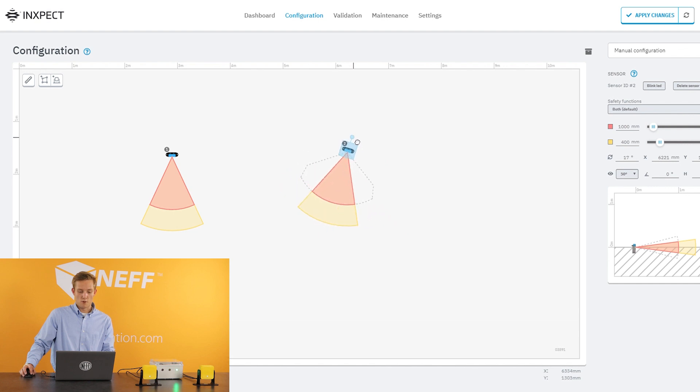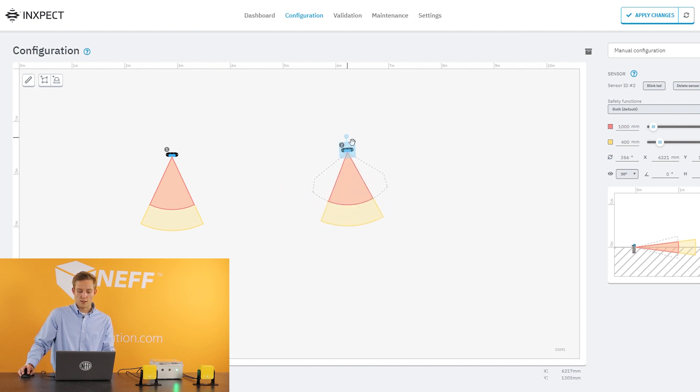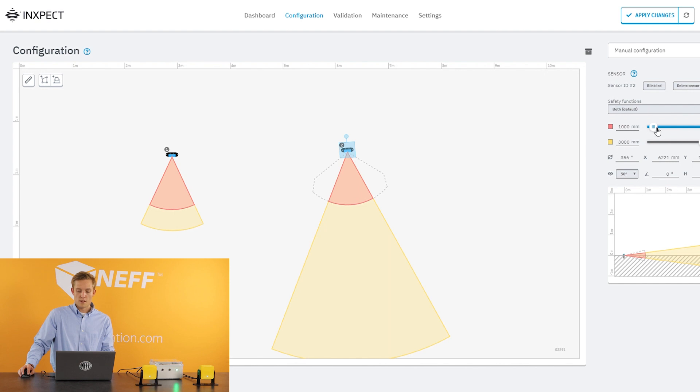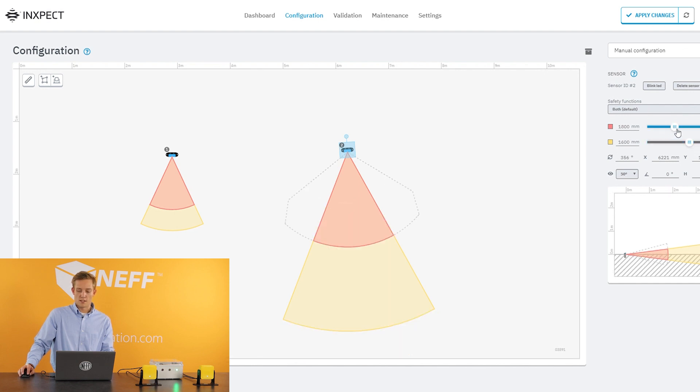You can see I can rotate them just like that, and then right here gives you the option to set your distances. So I can set my warning field all the way out to four meters, and then I can set... well it's three meters but it adds the one meter from the sensor here in your protective zone, and you can adjust those however you please. Same for your protective zone.